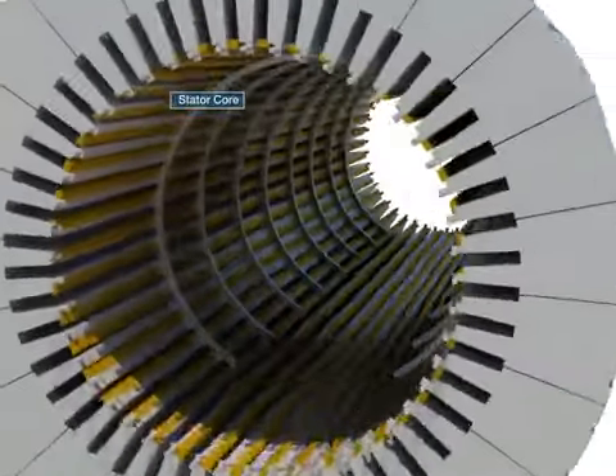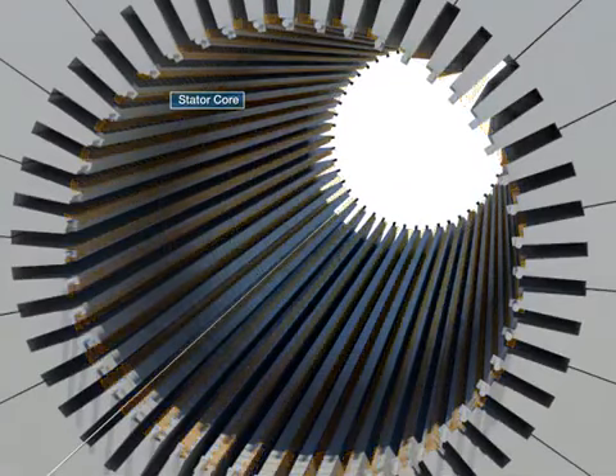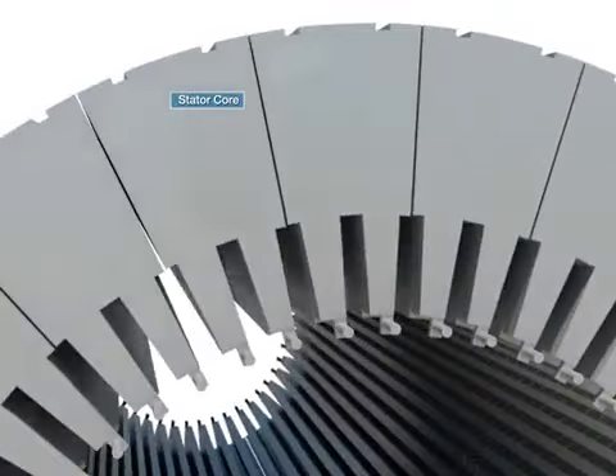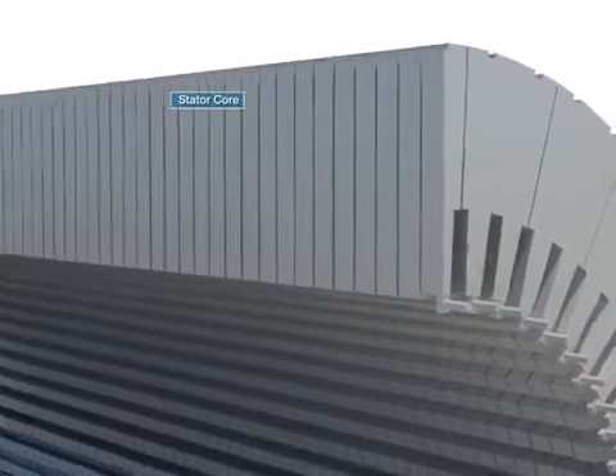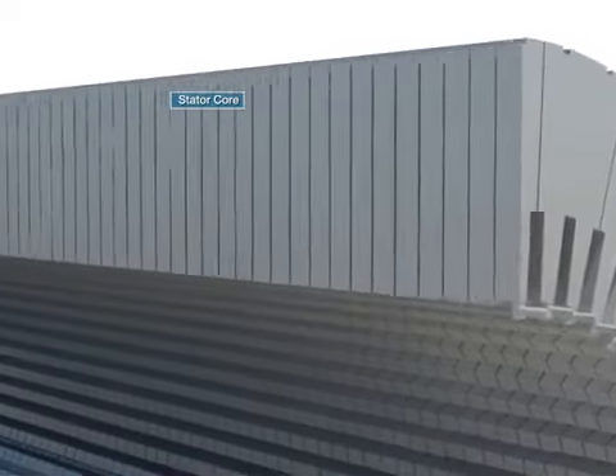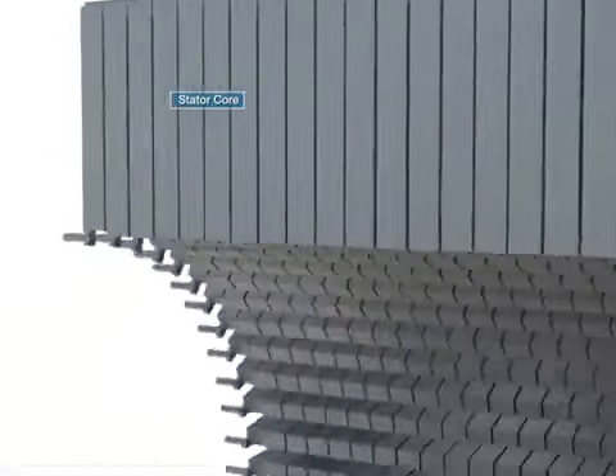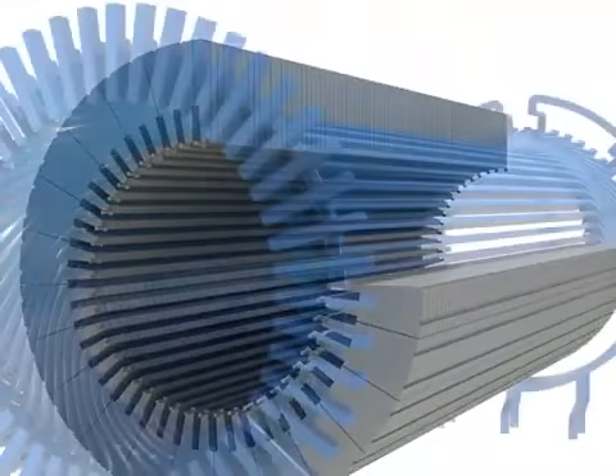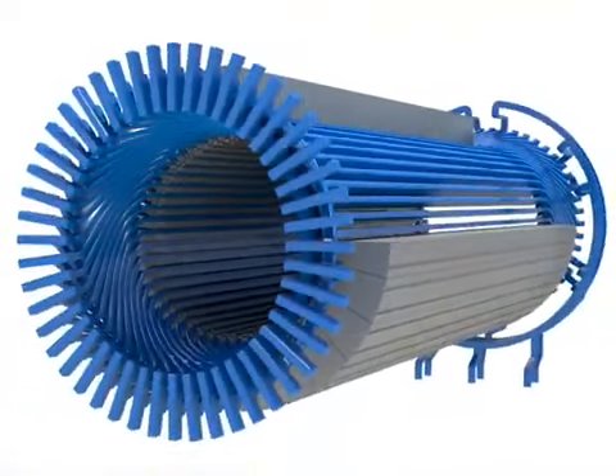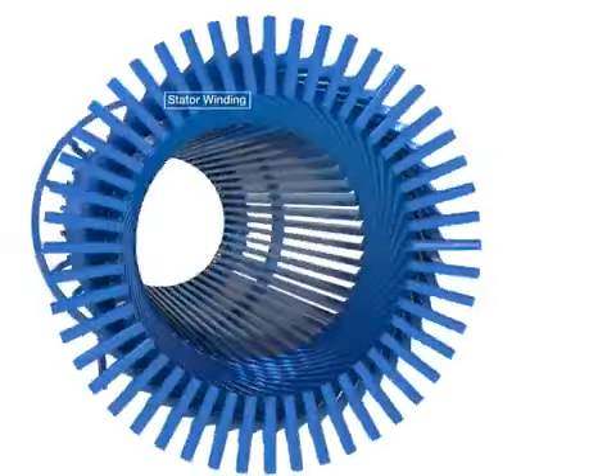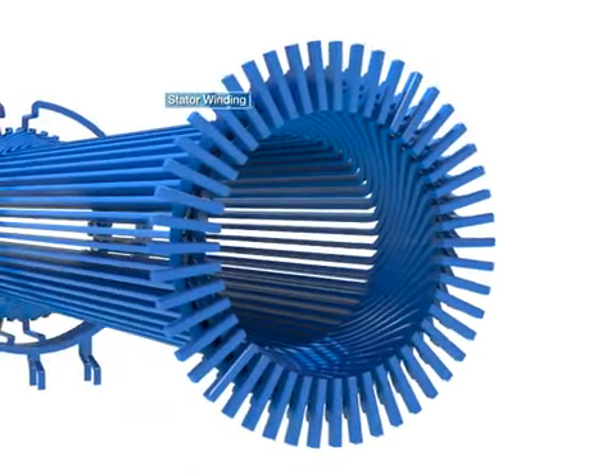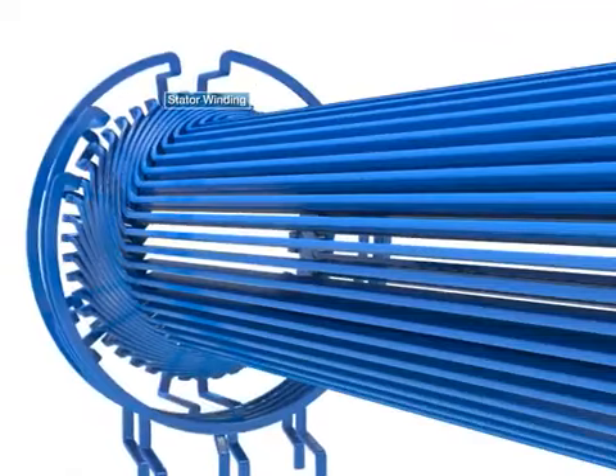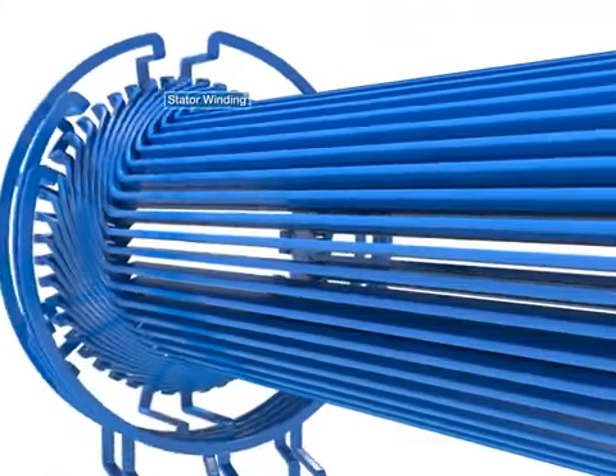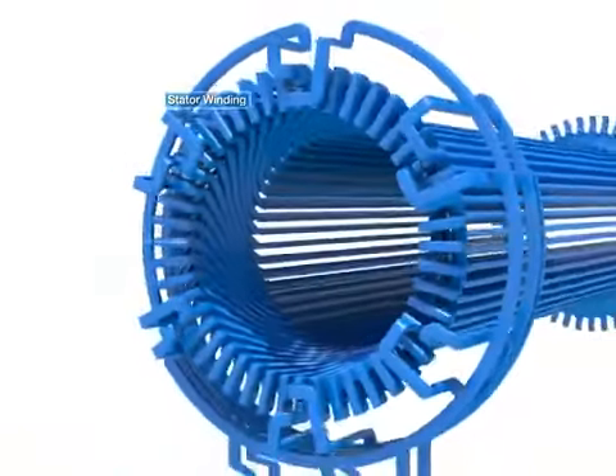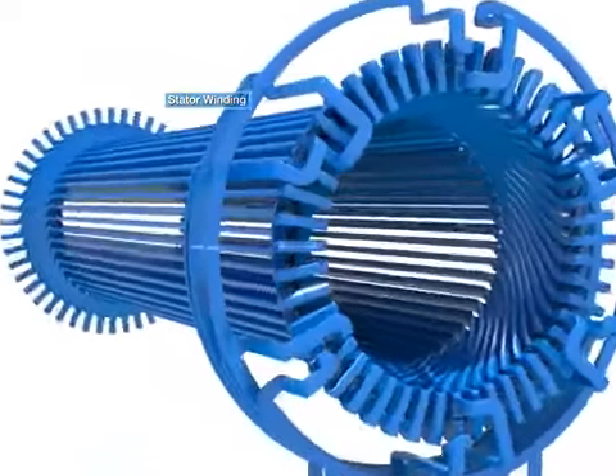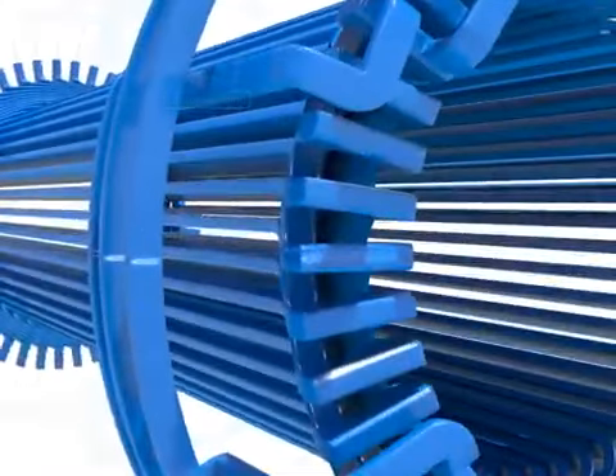The stator core provides a magnetic flux way, which connects the rotating field, and is made of cold-rolled silicon steel plate fan-wise and insulated to stratify it. The stator winding is made of half coils and is inserted in the slot of the stator core, then the ends are welded and it is used as flat-type copper wire. The stator winding interlinks with the magnetic flux provided from the rotor and generates electromotive force.